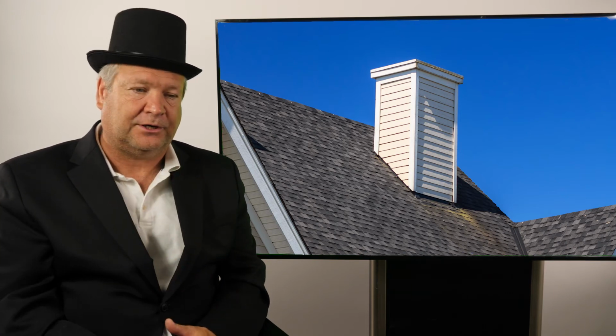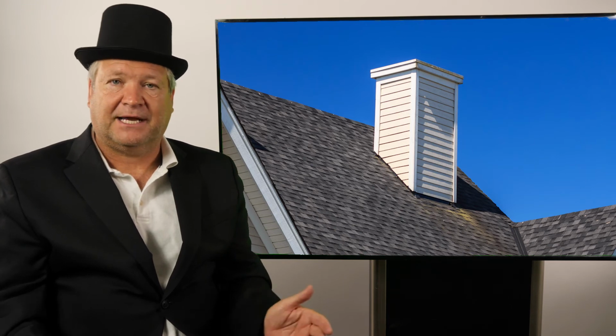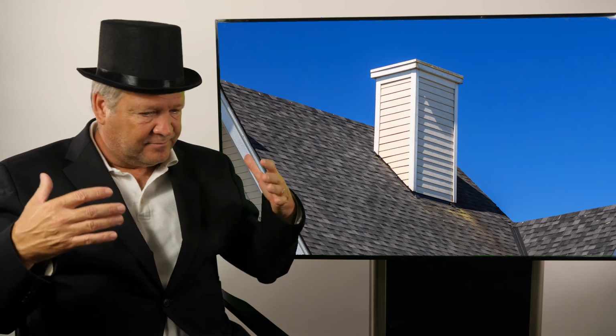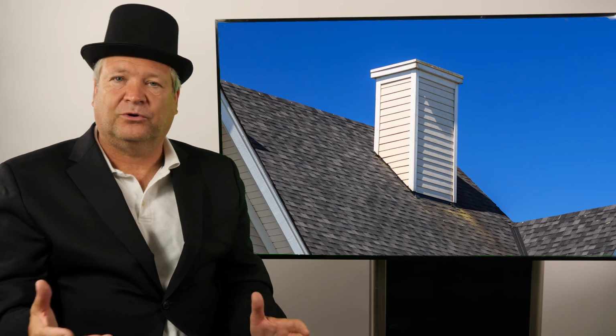If it's a hairline crack, you can fix it using refractory mortar. If it's too thick, or if it's wobbling or moving, then you're going to have to replace it. If the manufacturer's still in business, you might call up the manufacturer and just get yourself a new panel. If he's not in business, you might do these cut-to-fit refractory panels and put them in. There's some discussion whether that's right or wrong, but it is what it is. They're refractory panels. They are designed as a system. If they're 20 years old, I'd recommend getting a whole new one, but that's what you're dealing with.